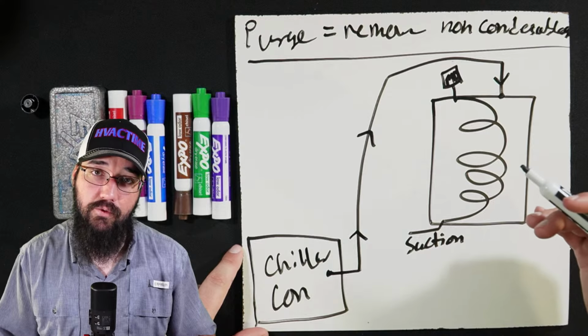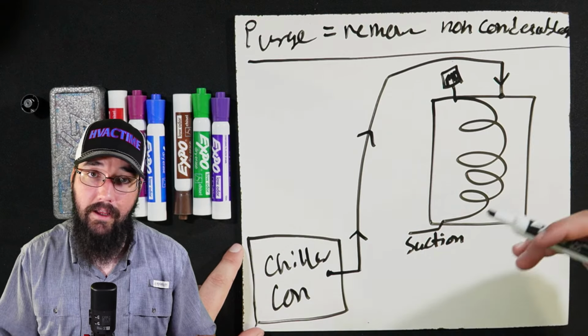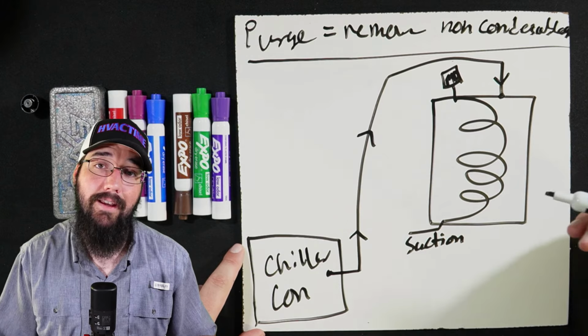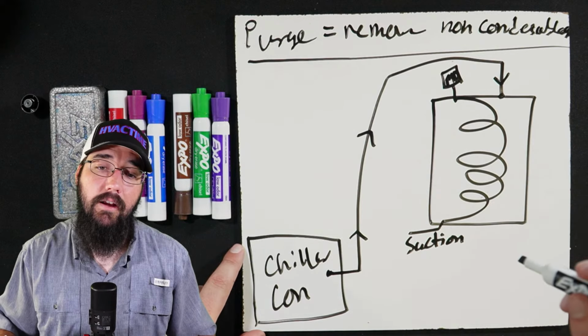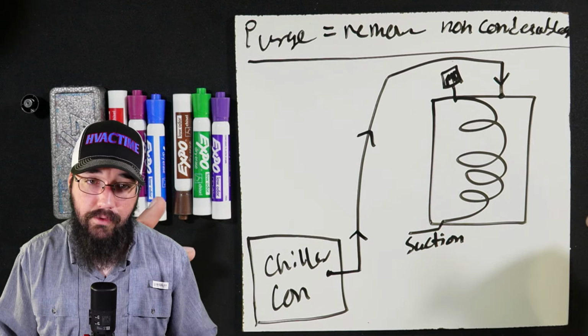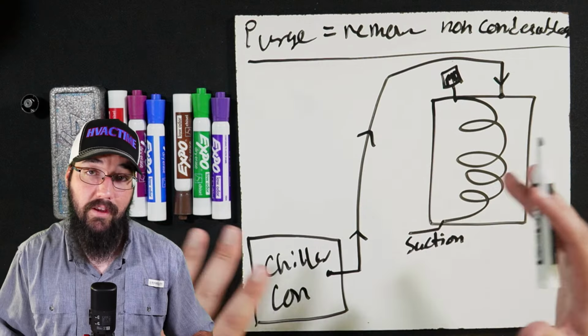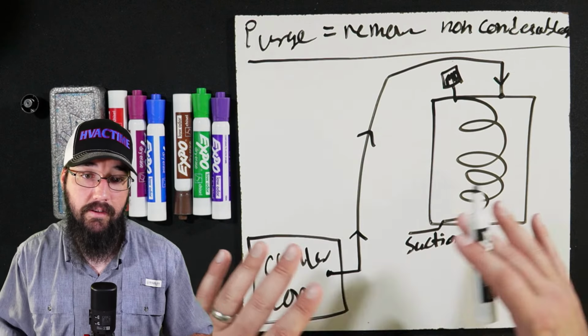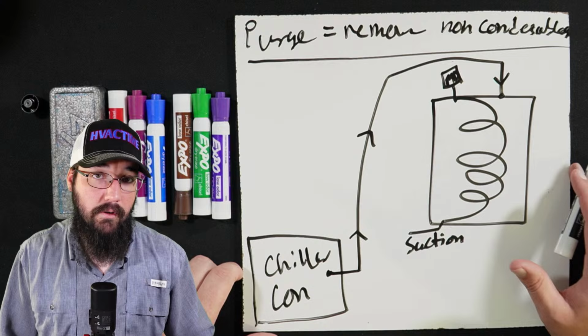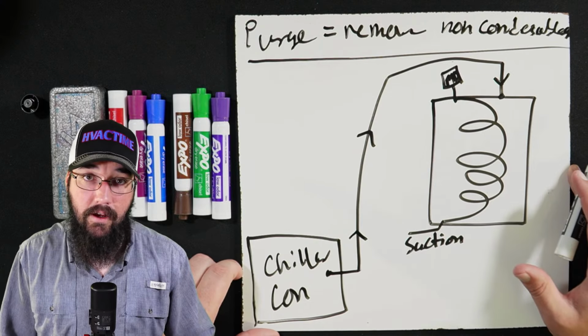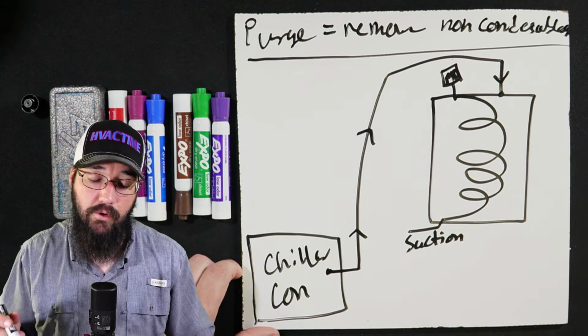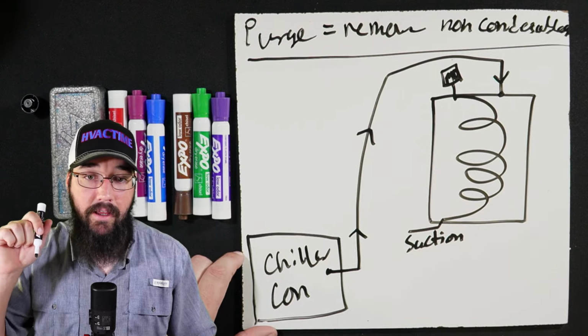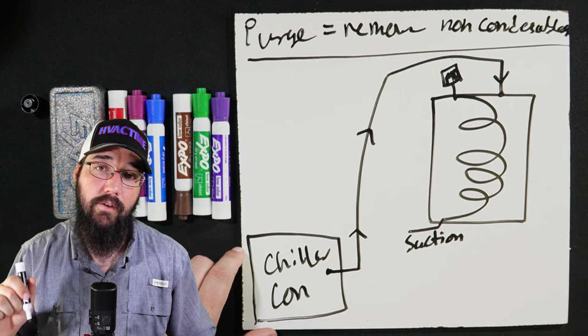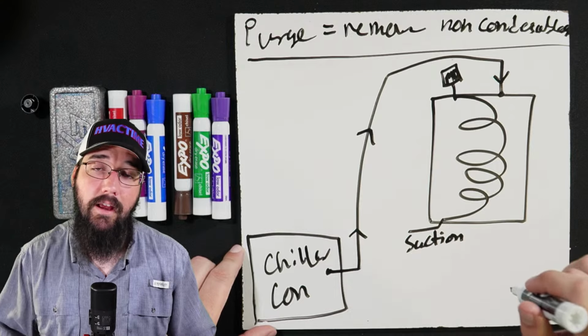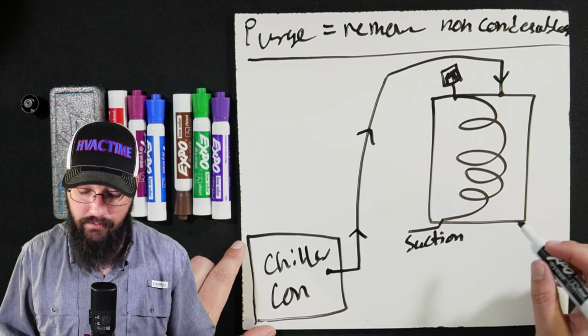These types of centrifugals are meant to run for days and weeks and months on end if they need to, right? Typically they don't. In comfort applications, they might. In industrial applications, right? They may run for months on end and never have to shut down. They don't need to shut down. So you have to keep that in mind, that all of these systems are made to where this machine doesn't need to turn off in order to process any of this refrigerant.